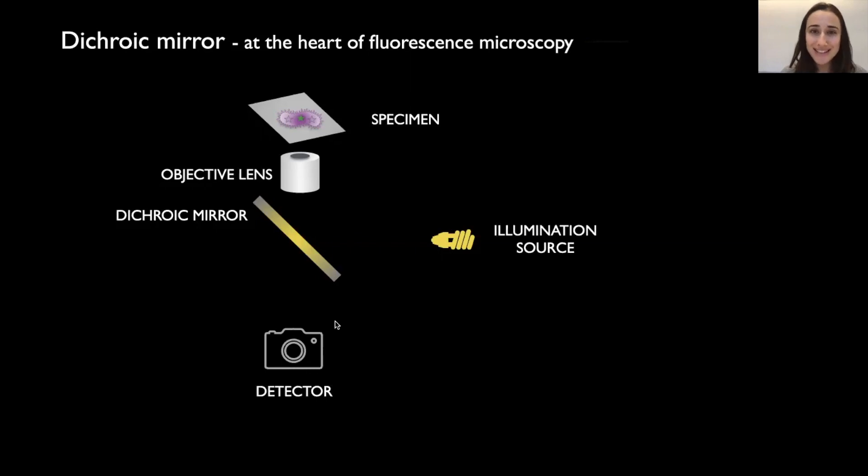So where does the dichroic mirror sit in our microscope? So for example, here we are depicting an inverted microscope because we are looking at our sample from below. So we have our sample of interest, the objective lens that sits underneath and the dichroic mirror sits at 45 degrees underneath the objective. And therefore, this dichroic mirror will be able to reflect the wavelengths of light that we are going to use to excite our sample, which then the objective collects the fluorescence and the dichroic mirror lets these wavelengths pass through, just the fluorescence, and discards the illumination wavelengths to the detector.